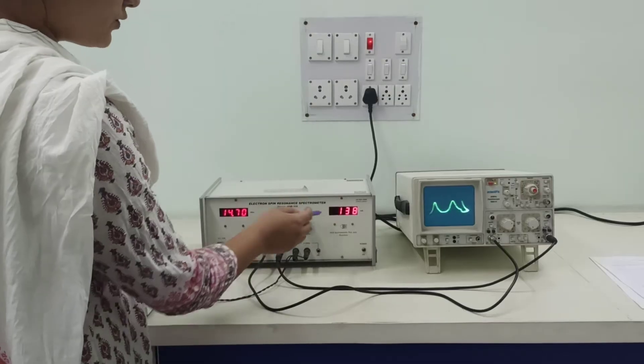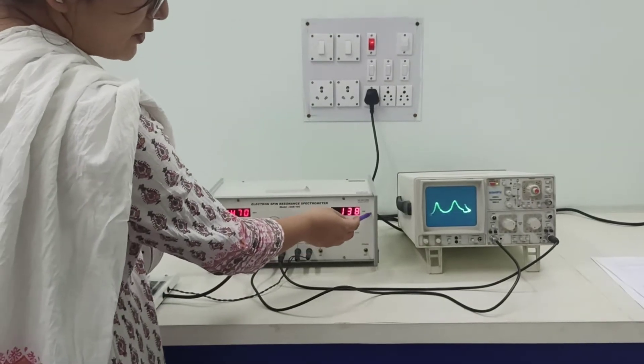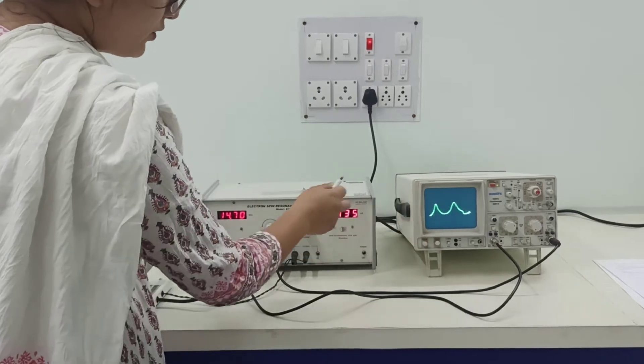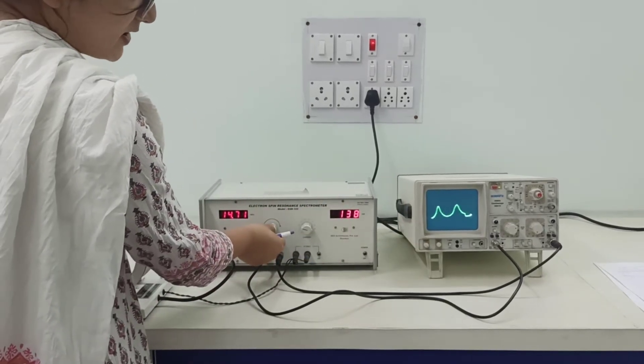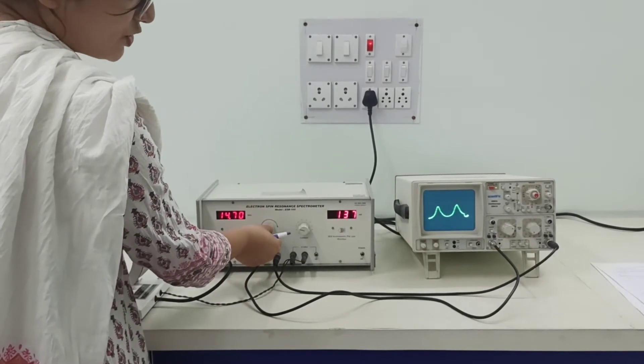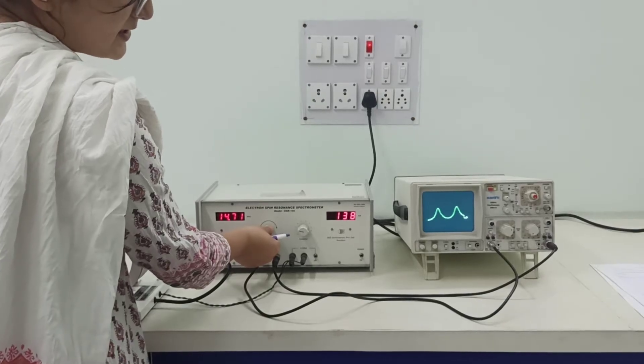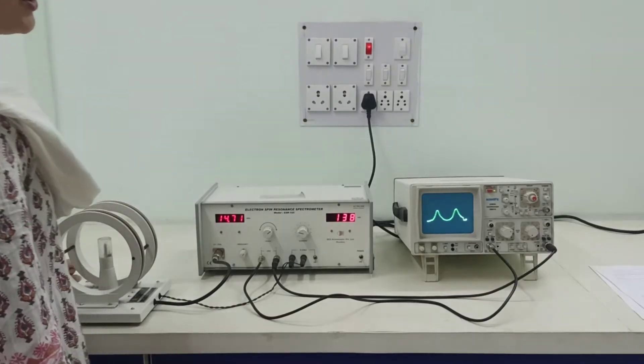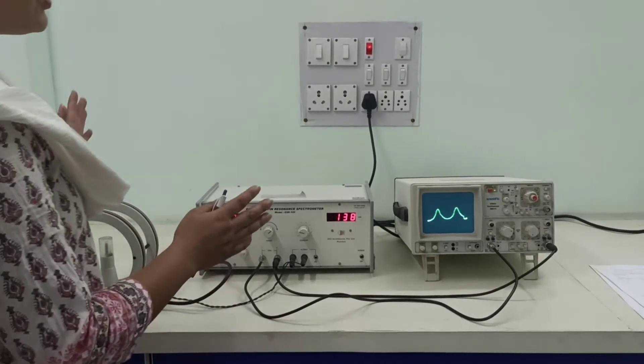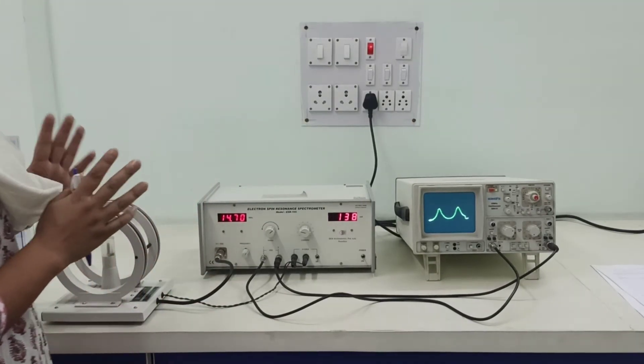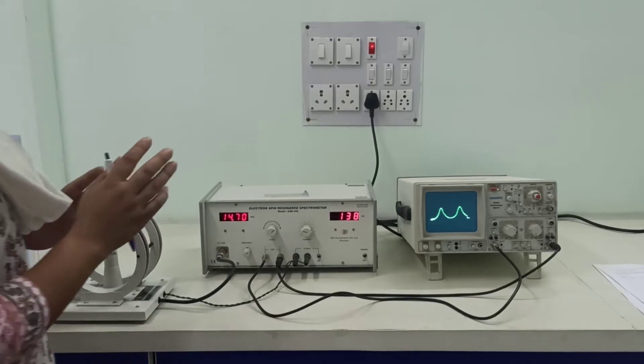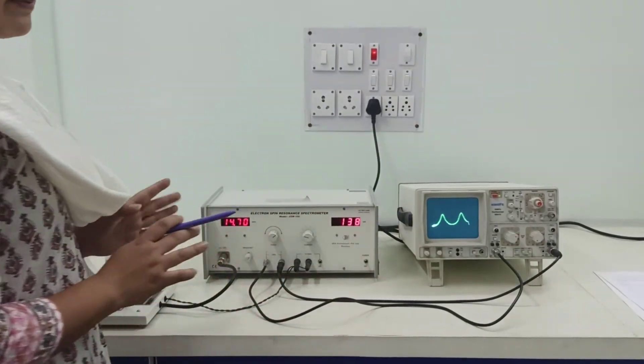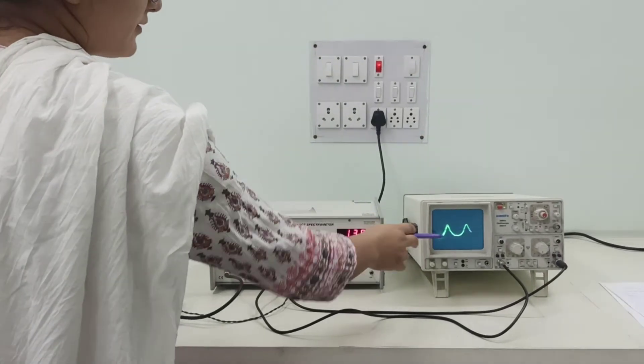So for 130 milliampere of current, we see two different peaks. Now, making use of this phase adjuster, we have to make sure that these two peaks, they overlap back to back, something like this. You should try to make the best possible overlap. They will not overlap exactly, but a rough overlap is fine. Something like this is fine enough.